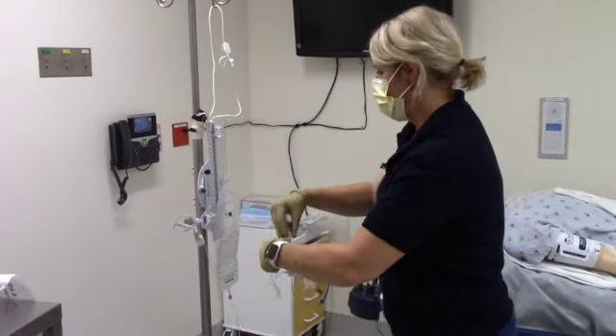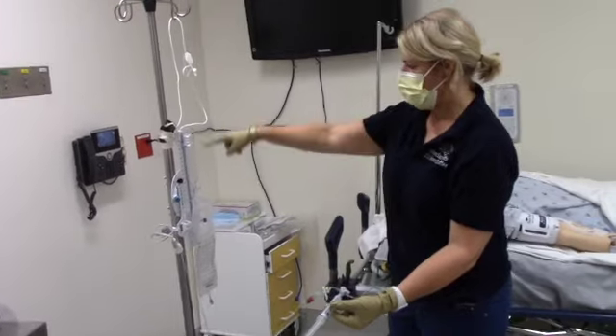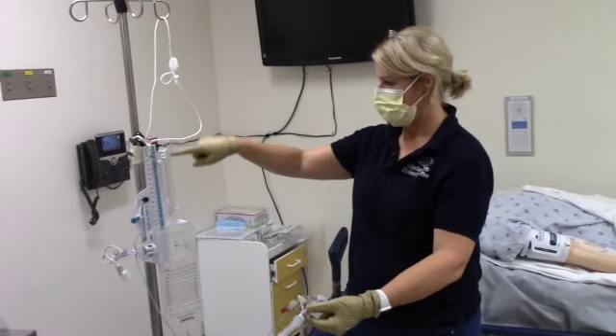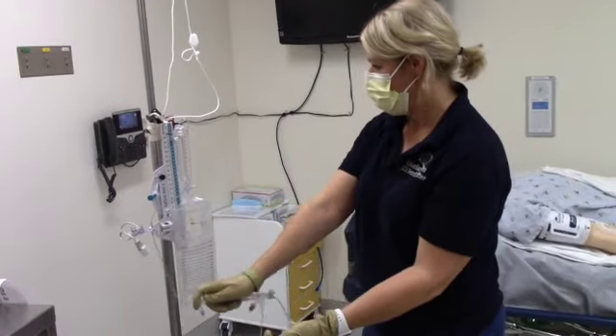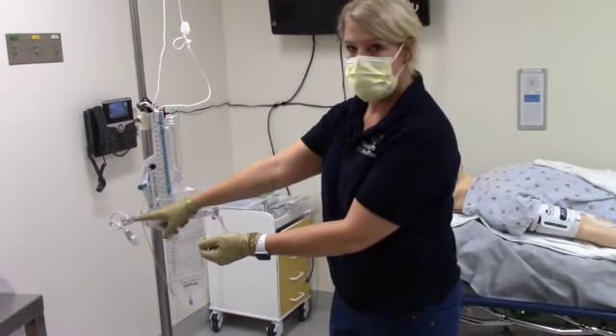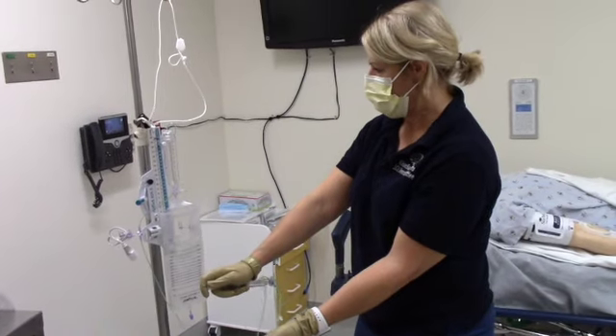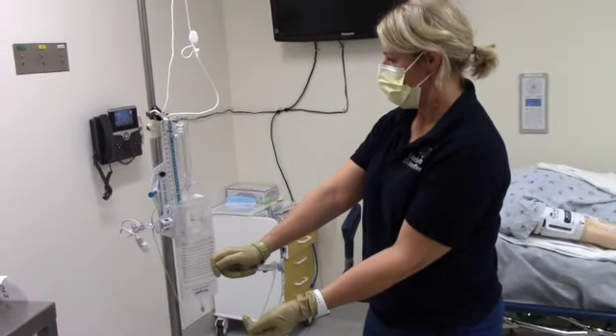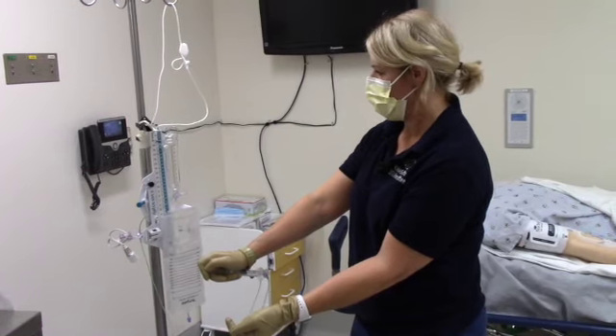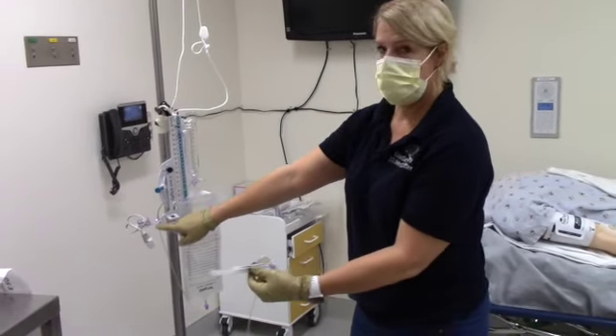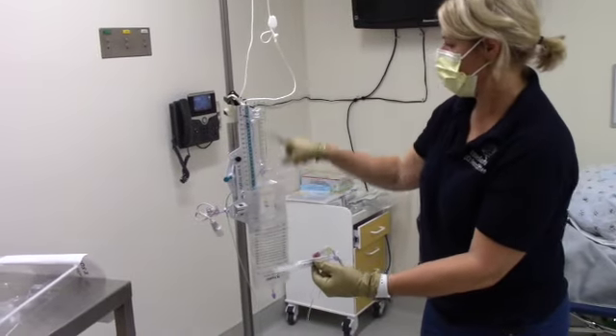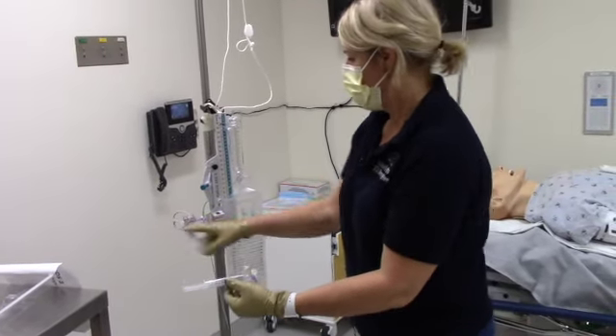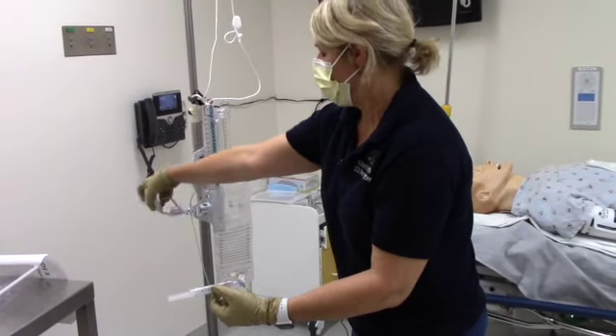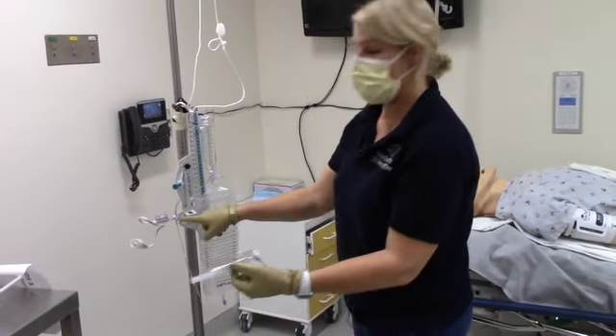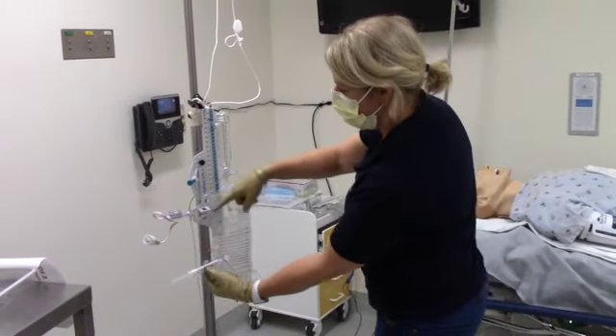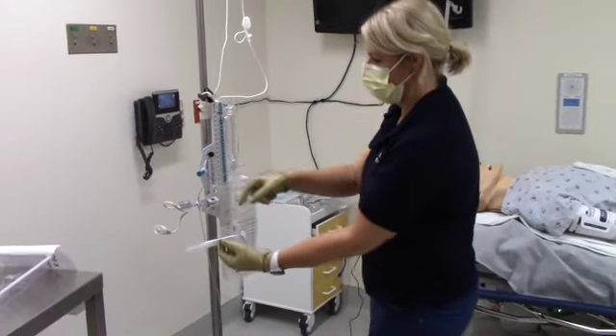Okay? The next step is to flush all the way to the buretrol itself. So this stopcock is off to the transducer. So all the way up until it drips. And then you will turn the transducer stopcock off to the Buretrol, and we're going to flush out the transducer. This stopcock will now stay this way indefinitely, and so I always remember it as they're going opposite directions.